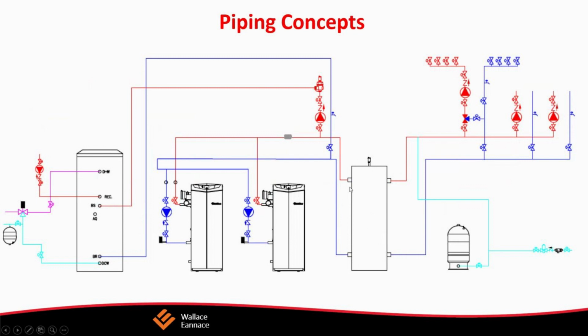So let's take a look at some other piping concepts. One of the things that we highly recommend is primary secondary piping. As you can see here, the expansion tank is connected to the bottom at this point, so that now all the system pumps are pumping away from this, and all the other pumps are pumping away from the expansion tank. You have the system expansion tank here. We've taken these indirect water heaters, and they're connected as a zone, and then all the other zones go out.